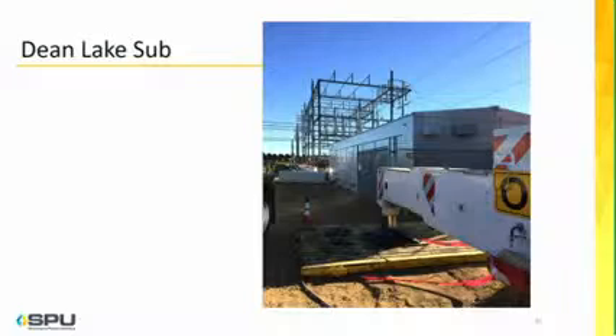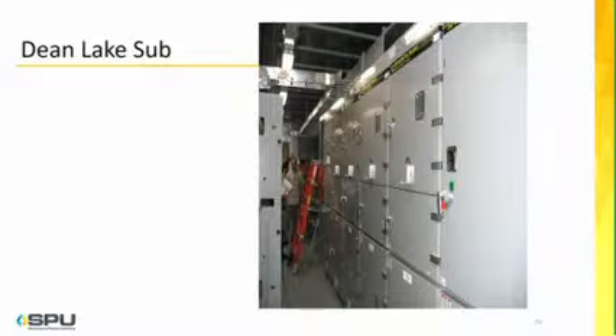This is an interesting chute coming out of here - if there are any faults, highly charged gases will be directed out away from any personnel, should a fault occur while someone's inside. We do a lot of remote switching now with our SCADA for safety reasons, but these are operable either locally or remotely.